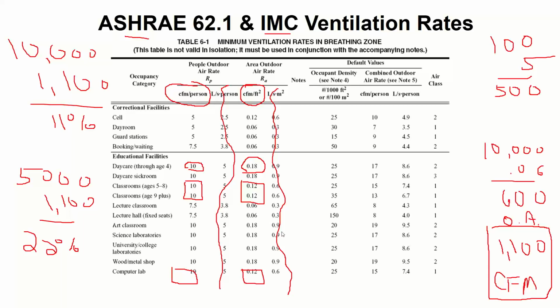There are trends to use natural ventilation in some LEED buildings, which often have it as an option alongside mechanical ventilation, but older buildings typically won't. A lot of schools with unit ventilators, by far the most common school design from the 1970s, 80s, and 90s, have units sitting on the wall below the window, like a shelf with a vent on top. On the back side there are louvers that suck outside air in. So when you walk outside a school and see that little louvered panel under each classroom window, that's the fresh air being drawn in. That's the most dominant school design from the 1970s and later.